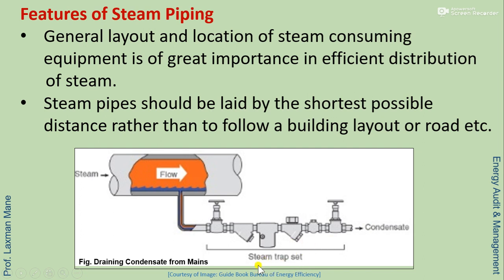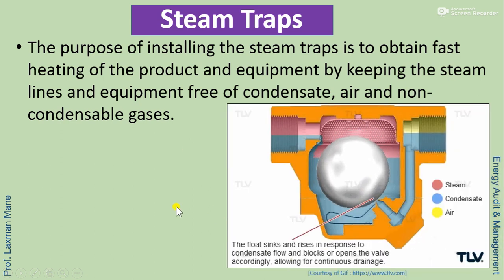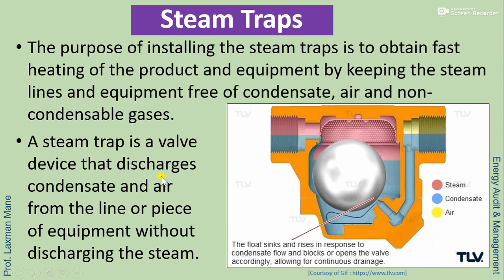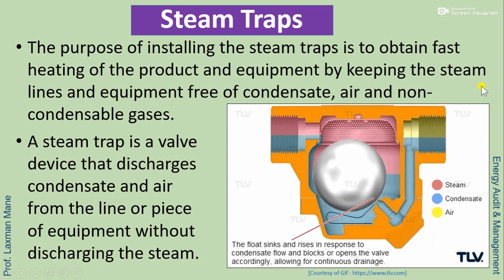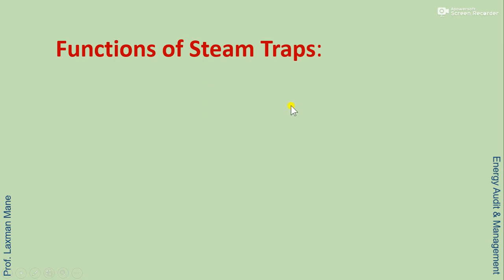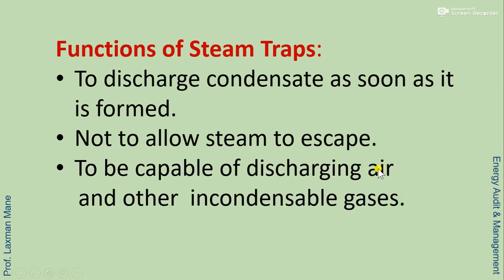A steam trap set is shown in this image. The purpose of installing steam traps is to obtain fast heating of the product and equipment by keeping the steam lines and equipment free of condensate, air, and non-condensable gases. A steam trap is a valve device that discharges or removes condensate and air from the line or piece of equipment without discharging the steam. The functions of steam traps are: to discharge condensate as soon as it is formed, not to allow steam to escape, and to be capable of discharging air and other non-condensable gases.